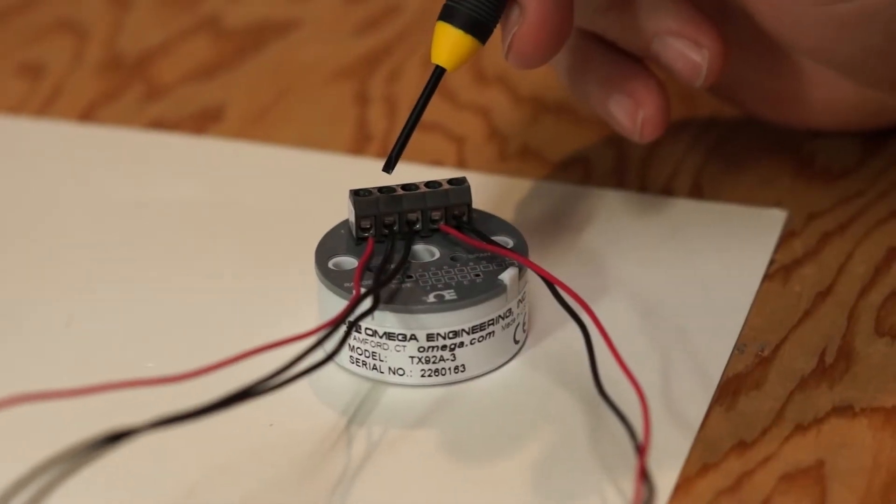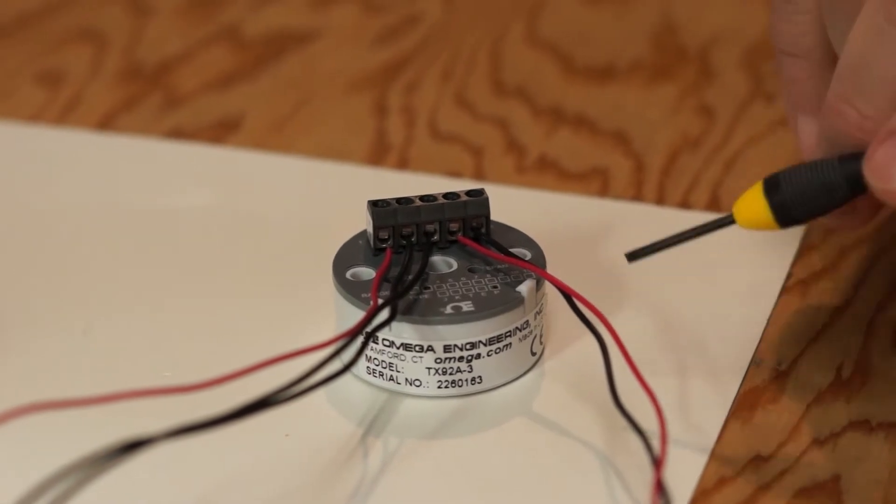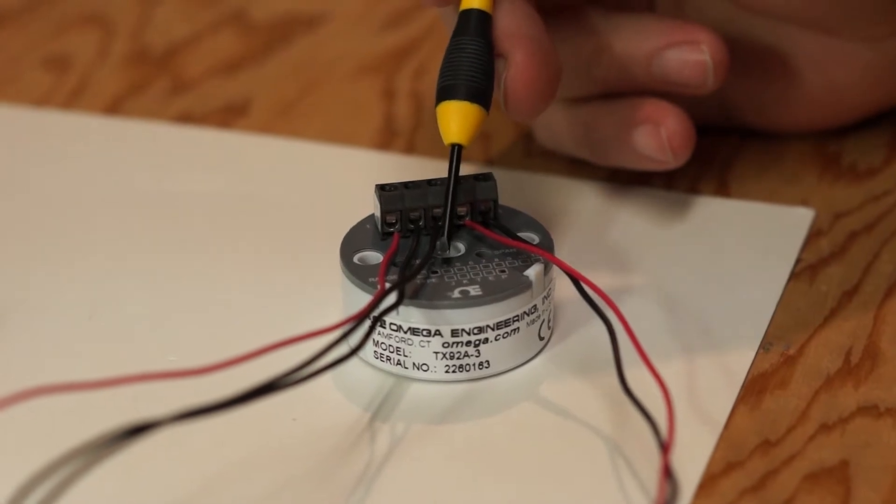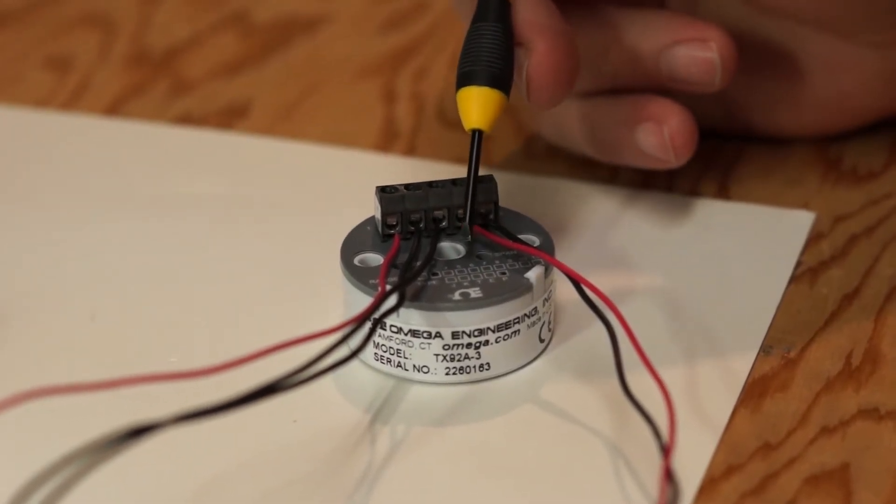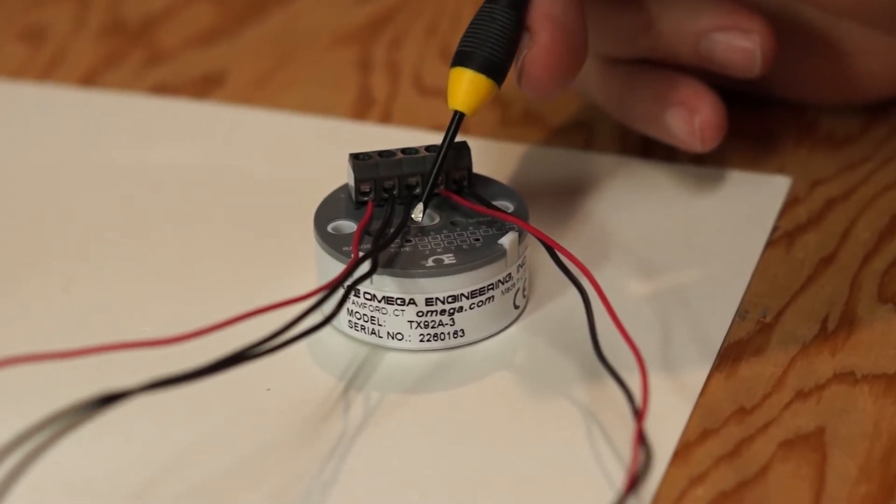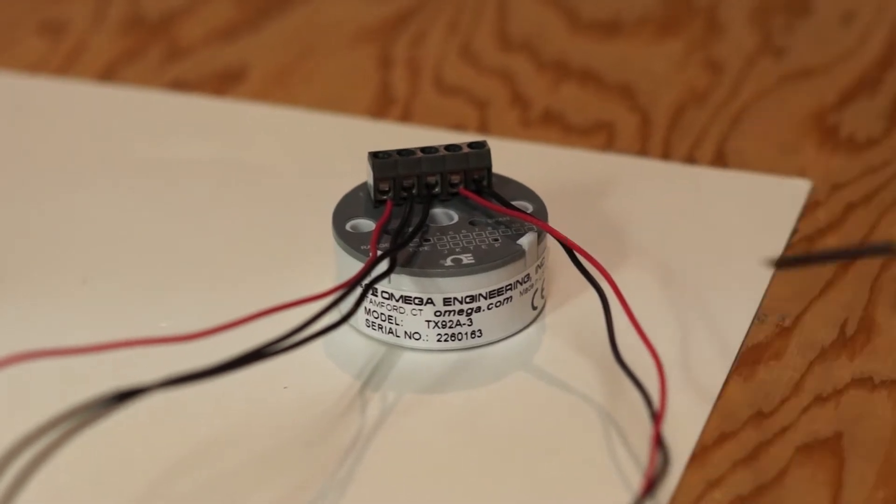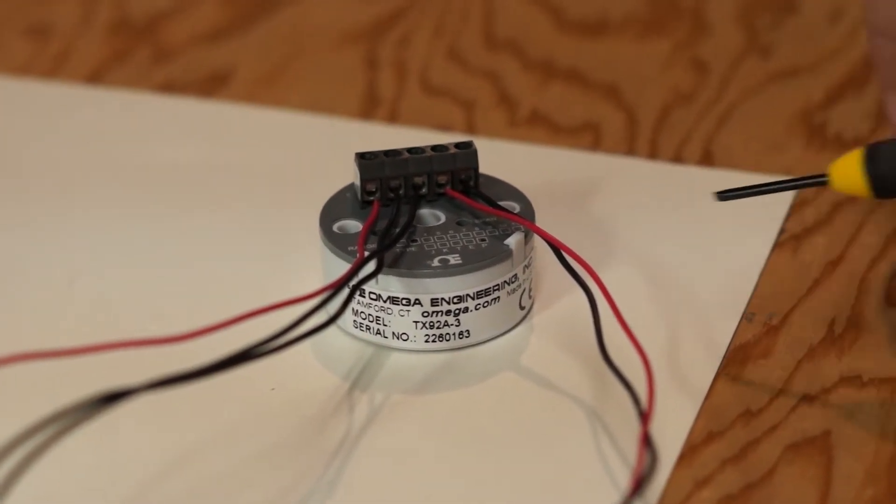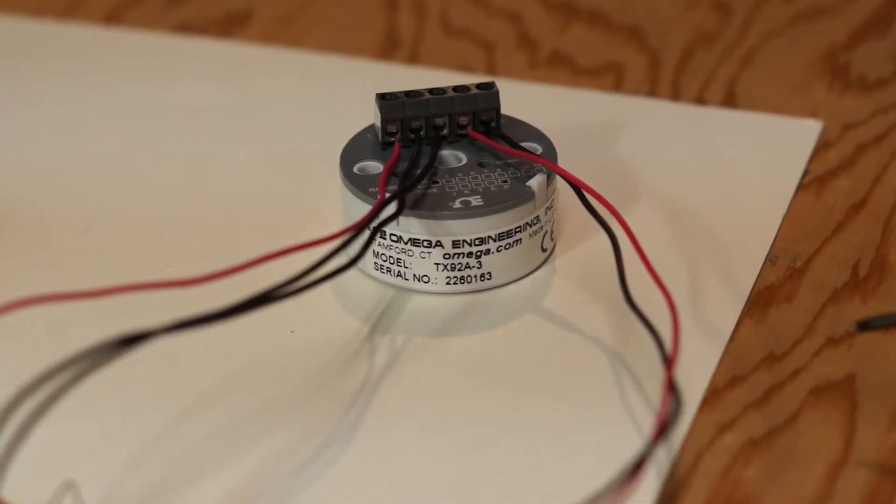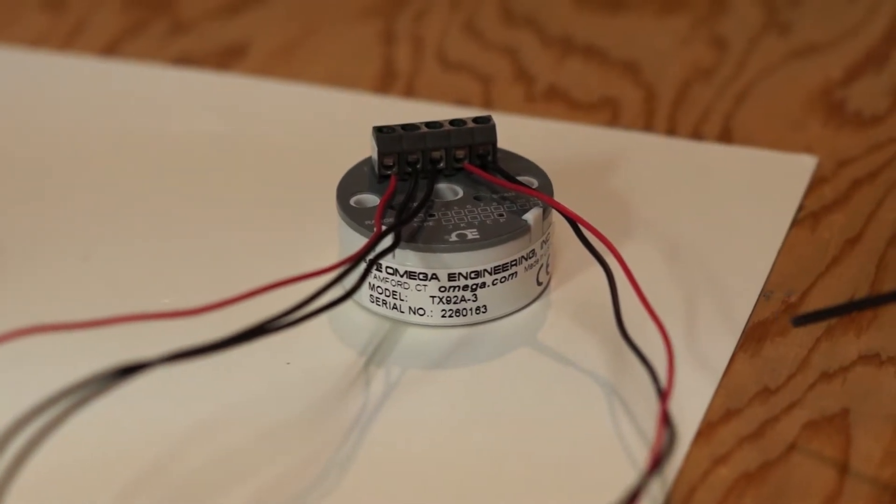So here we have the transmitter and this type is a transmitter for RTDs. It's white in color and if you recall the thermocouple is yellow in color. You can even see on the top the label here indicates that it's a type 3 which means it goes from 0 to 300 Fahrenheit and it indicates the little letter P is black in there to indicate it's a platinum RTD transmitter. Now down at the bottom here you'll see the name, it's a TX92A-3. You will have a data sheet that you can look up the information for that.